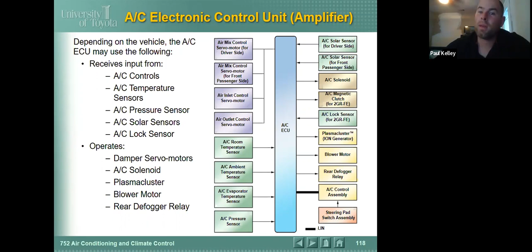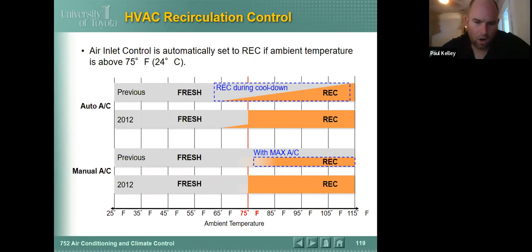So consider these things when we're talking about automatic temperature control. Think about if the sensor would cause it, how you can check the sensor to qualify it, to see if it's good or bad. Temperature sensors to me are easy: access the sensor, measure the resistance of the sensor, compare it to live data, and boom.